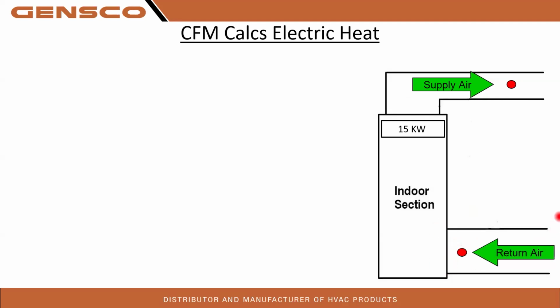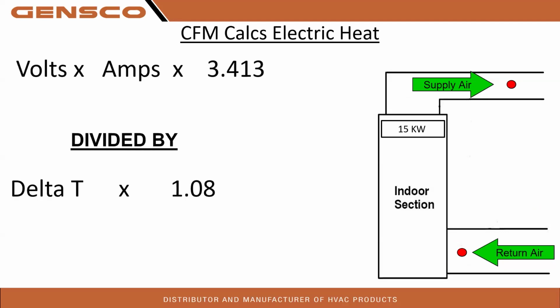I have seen people just take them at the registers, which you don't get a true average of what that indoor return is doing, because it could be 73 at one position. And then if we've actually got an outside air open to 32-degree air, this is going to be registering like 50 degrees. Okay, so it's going to throw you off big time. And if you're pulling in 70 degrees or 73 at one return air, this should be pretty close to 73. And then, of course, multiple stories through the house.